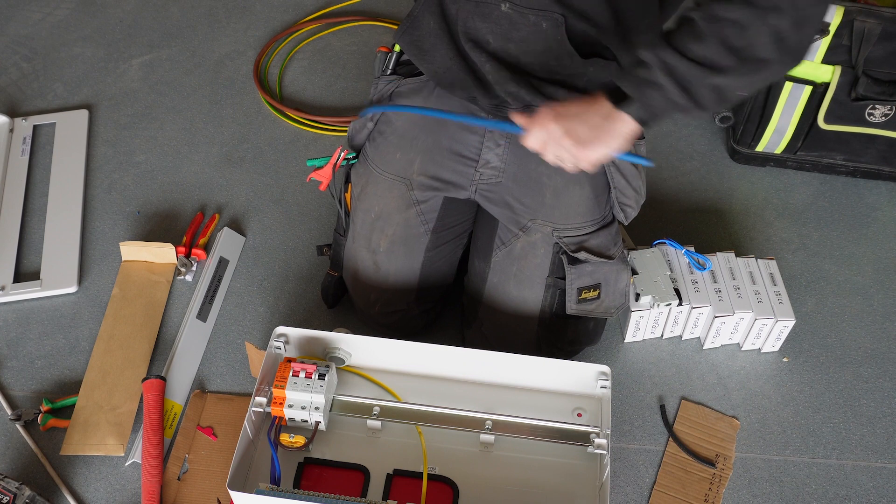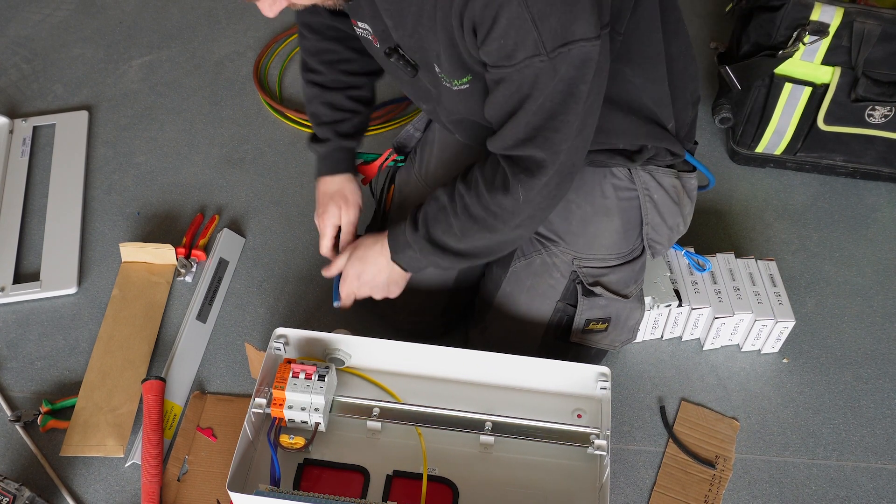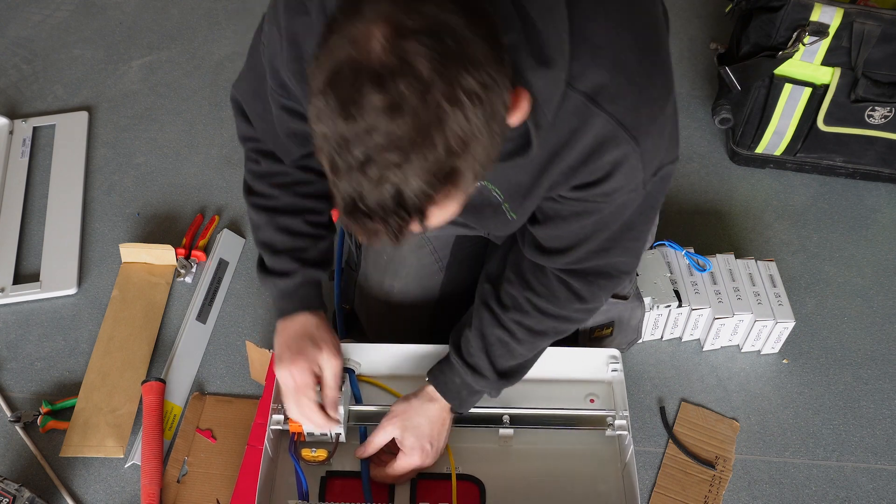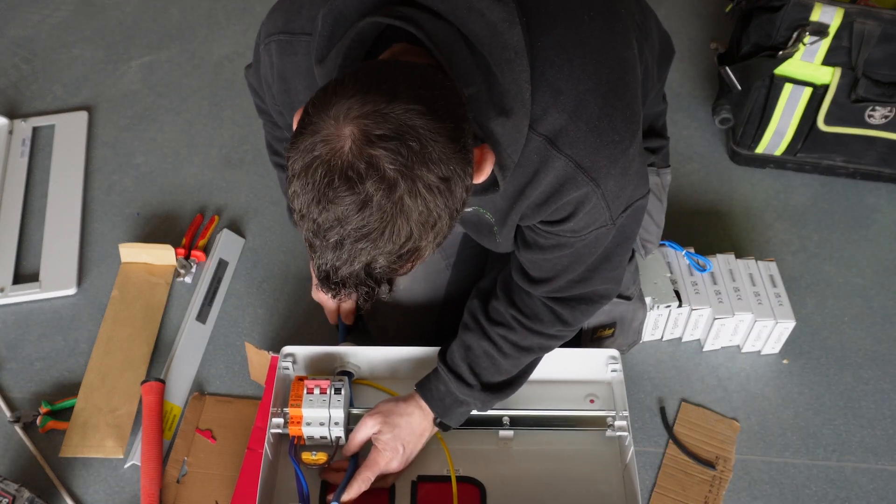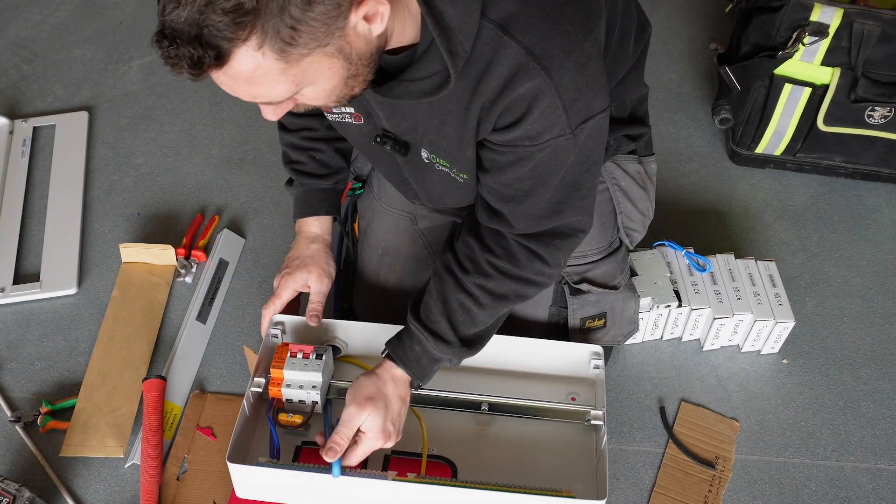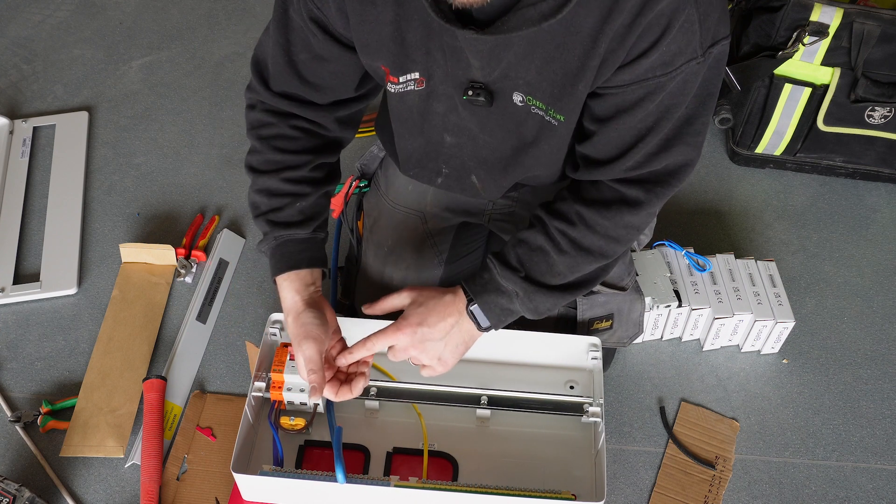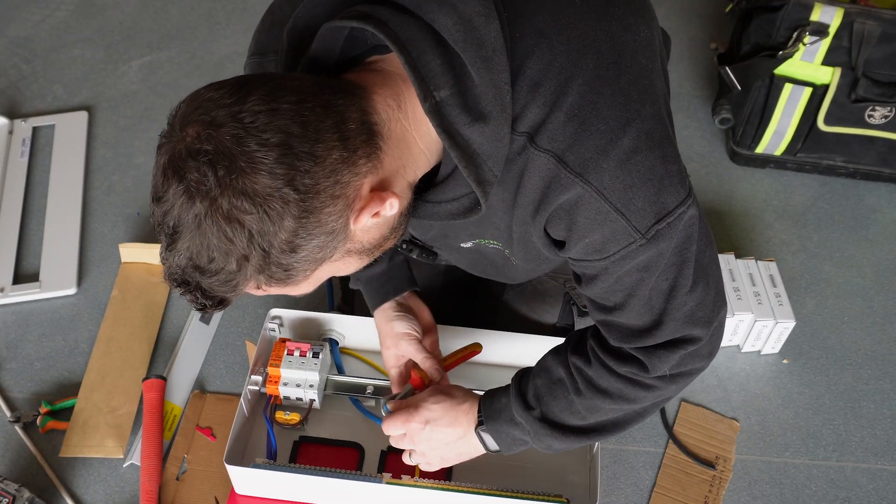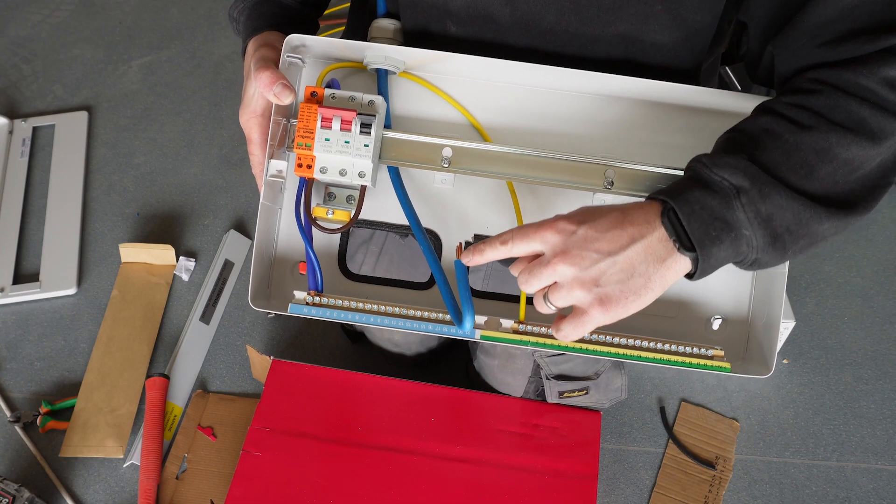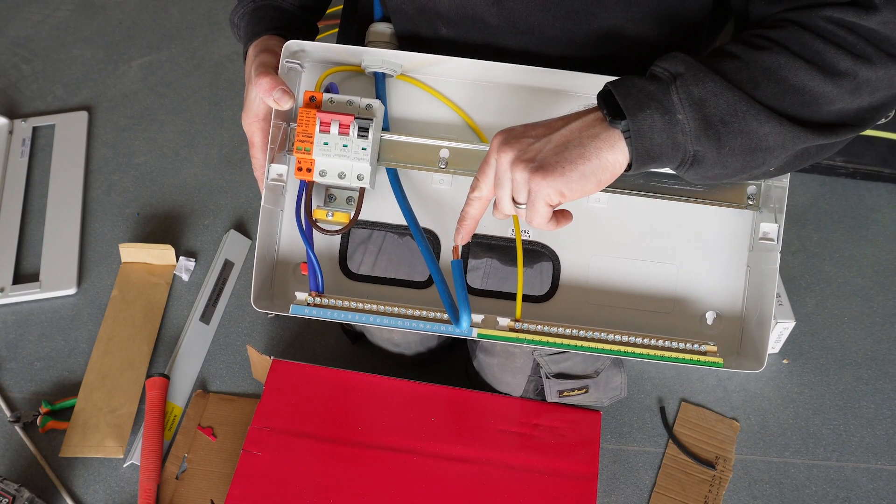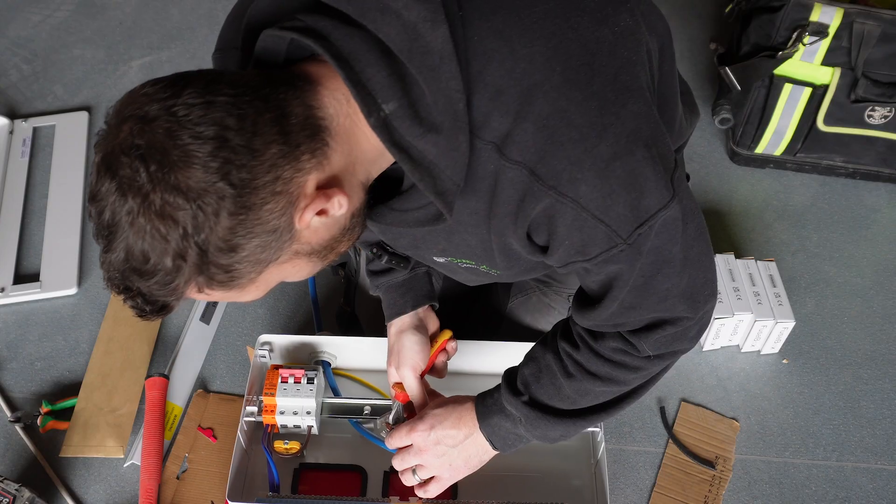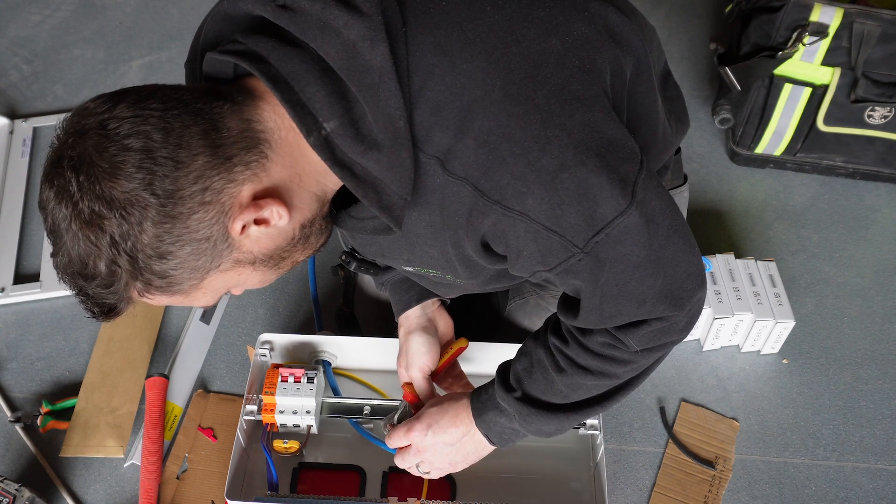I always start with the actual neutral itself. I always bend it over sort of a palm's width. As you've bent it, you'll notice that some of the cores are all on different lengths now, whereas they weren't before. You need to make sure that they're all flat and level.